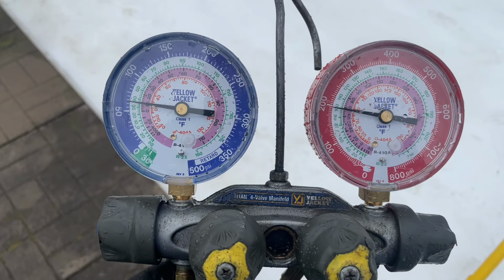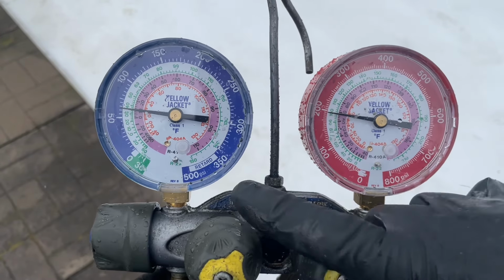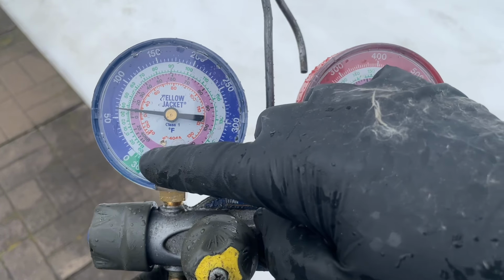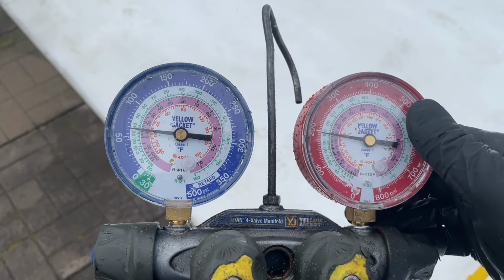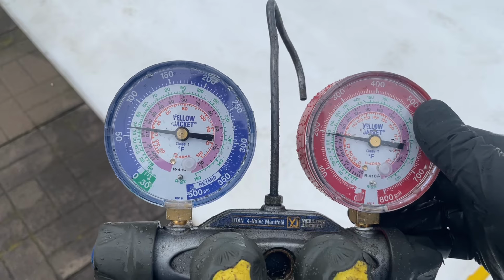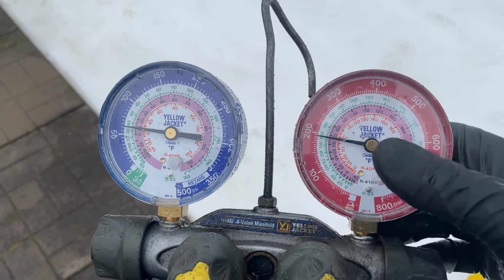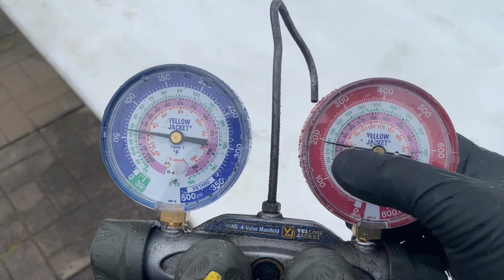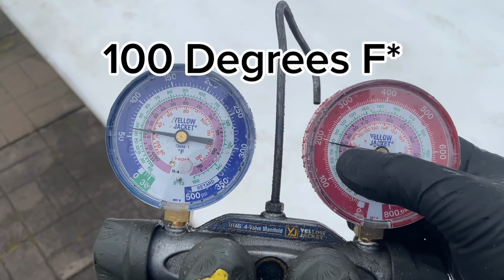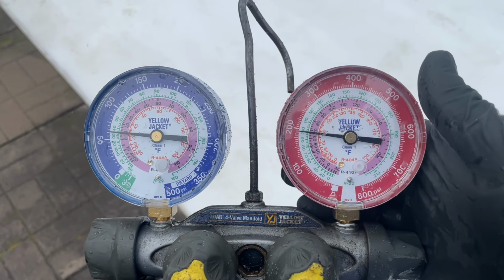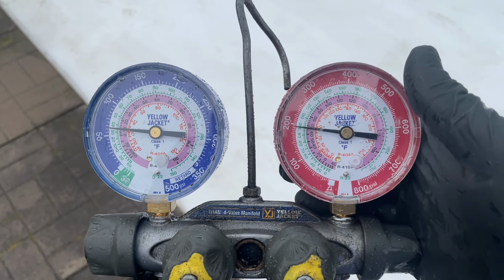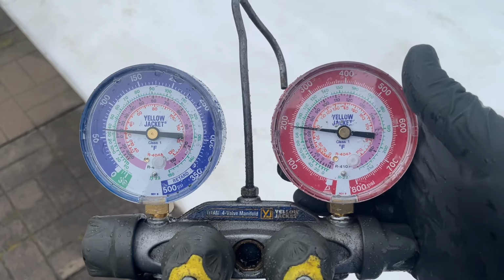All right guys, gauges are on. We're running on our 22 scale here, our green scale. Indoor coil temperature, 36, 38 degrees. Head pressure around 200 PSI. It's about 70 degrees Fahrenheit. It was down in the space a minute ago. It wasn't overly hot because today it's rainy and kind of mild, but this unit's running great.